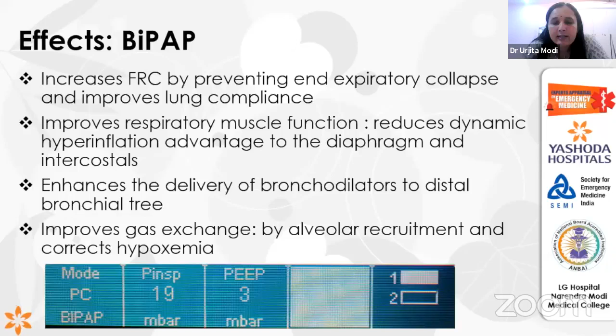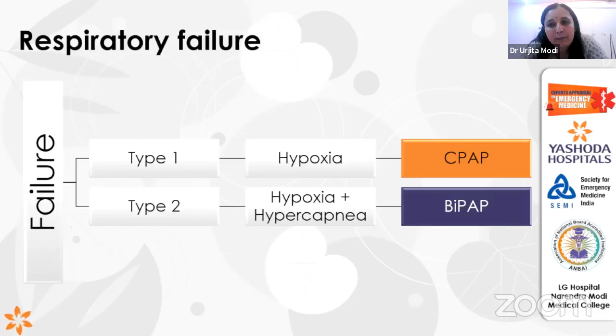Again, to summarize the whole thing, in CPAP, as we already discussed, there is continuous positive airway pressure throughout both inspiration and expiration, or throughout the cycle, in spontaneously breathing patients. The setting would be 5 to 12 centimeters of water. It is mostly indicated in type 1 or hypoxemic failure like cardiogenic pulmonary edema or CHF. In case of BiPAP, we have two components, IPAP as well as EPAP. IPAP is set roughly around 10 to 20 centimeters of water, and EPAP around 5 to 10 or 5 to 12 centimeters of water. It is more useful for hypercapnic or type 2 failure.